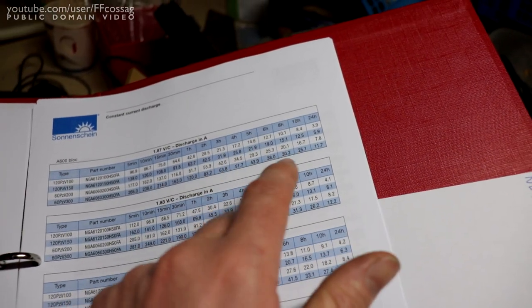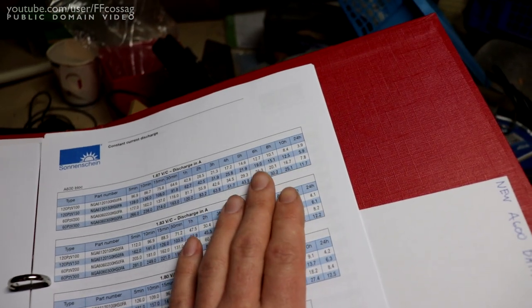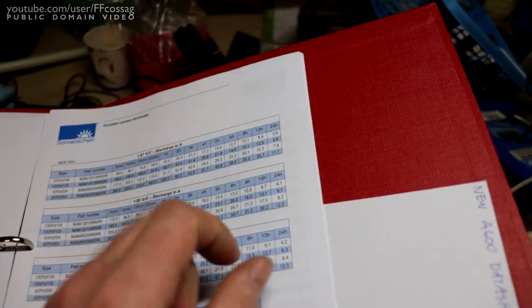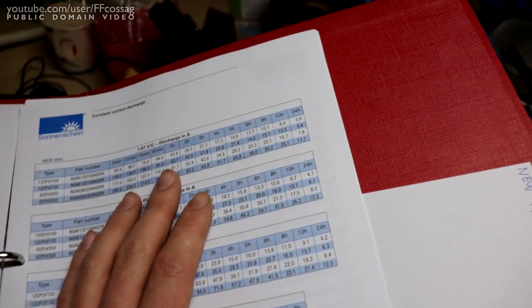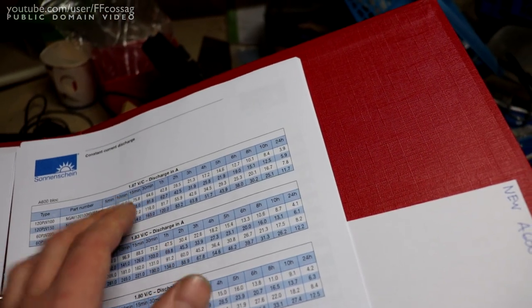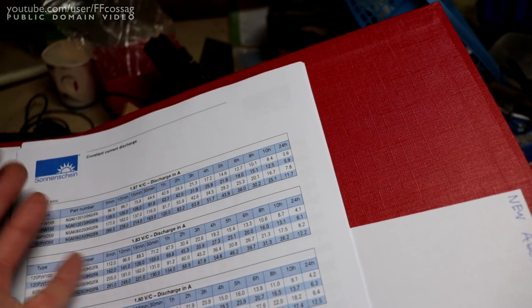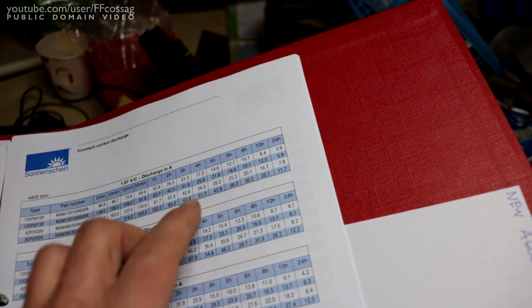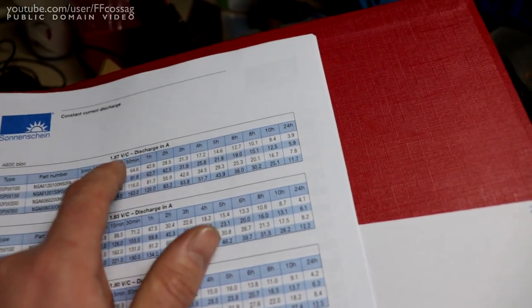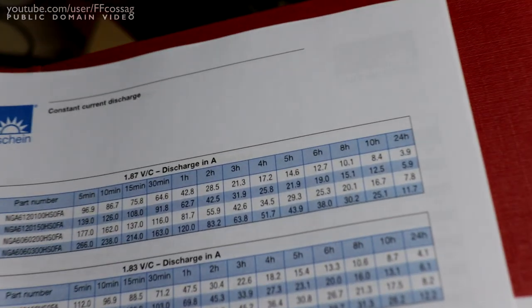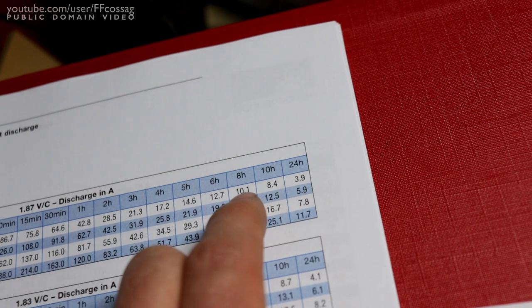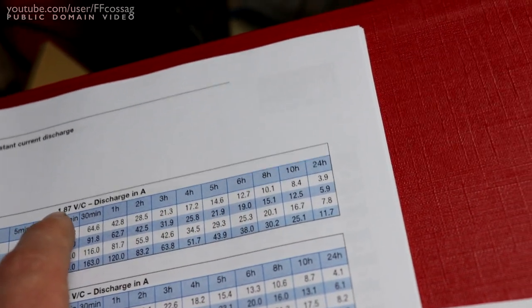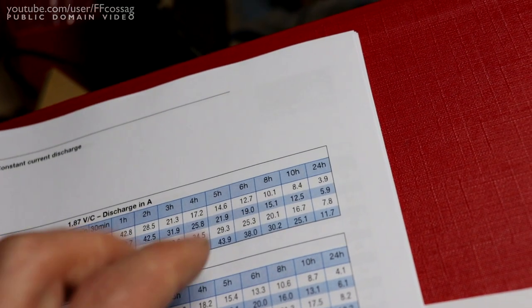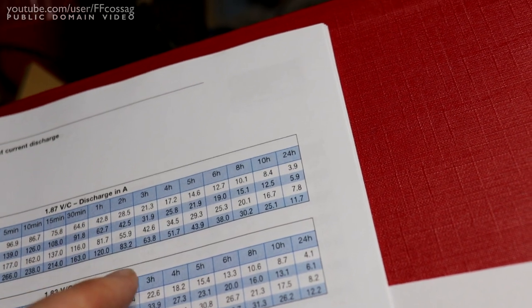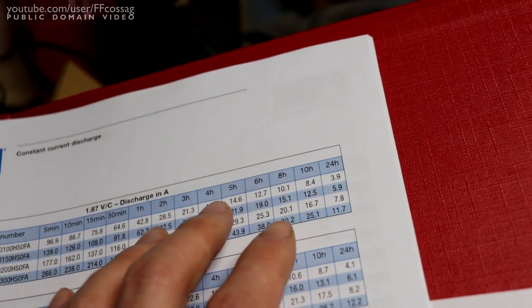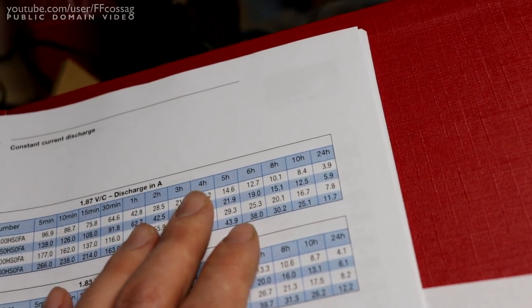So to get a good easy test that's easy to compare to the datasheet, my tester does 10.0 amps. So I've been scouring this datasheet to see what kind of discharge end voltage and current I can do to get as close to 10 amps discharge as possible, so we can easily compare to this chart where we lie. And we can see at this 1.87 volts per cell discharge, we can do 8 hours at 10.1 amps. So I'm going to do a discharge to 1.87, which is 11.22 volts per block, which is a relatively shallow discharge. But that's going to make it easy to just calculate our percentage of remaining capacity in these batteries.